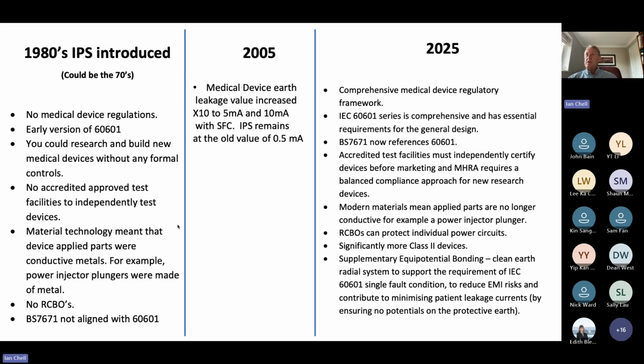So compared to 10 years ago, something big has changed. Devices are now extremely safe, including research ones. And also we have modern materials, which mean applied parts are no longer conductive. For example, a power injector's now got really impressive mechanically strong plastic. We have RCBOs, which can protect individual power circuits. And in theatres everywhere, we have significantly more class 2 devices, no protective earth. And supplementary bonding is much better now.